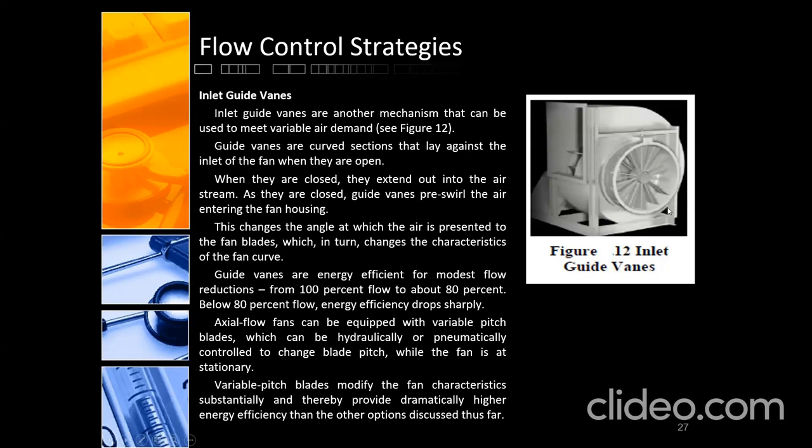Inlet guide vanes. So, inlet guide vanes yan, are another mechanism that can be used to meet variable air demand. See figure 12. Guide vanes are curved sections that lay against the inlet of the fan when they are open. When they are closed, they extend out into the air stream. As they are closed, guide vanes swirl the air entering the fan housing. This changes the angle at which the air is presented to the fan blades, which in turn changes the characteristic of the fan curve. Guide vanes are energy efficient for modest flow reduction, from 100% flow to about 80% flow. Below 80% flow, energy efficiency drops sharply.